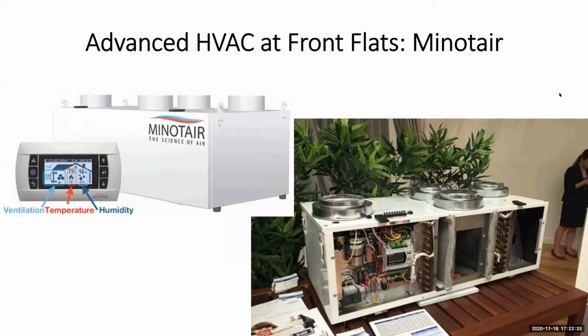So cool. Can I ask a question? Yes. If you are introducing this 250 CFM dedicated kitchen exhaust hood fan, when it's running, where's the makeup air coming in from? Is it all just squeezing in from your airtight envelope, or is it coming through the fresh air duct that's connected to your ERV? It's probably coming through your fresh air duct through your ERV.